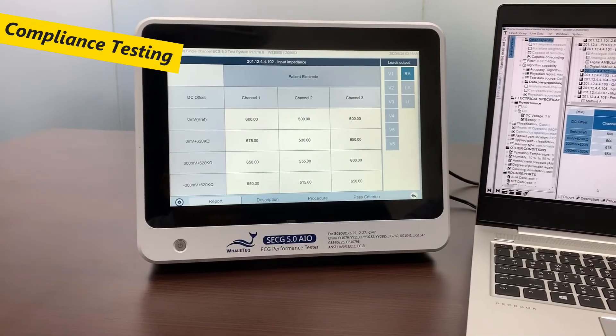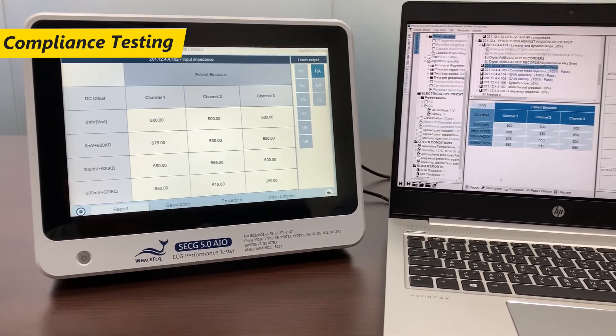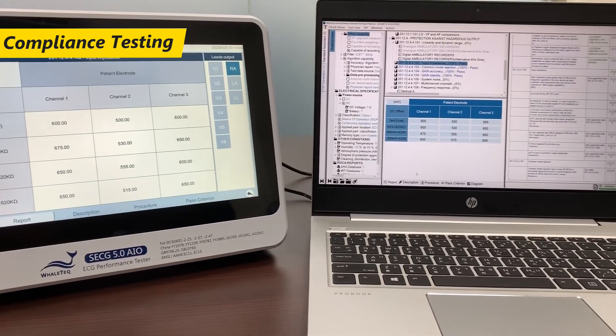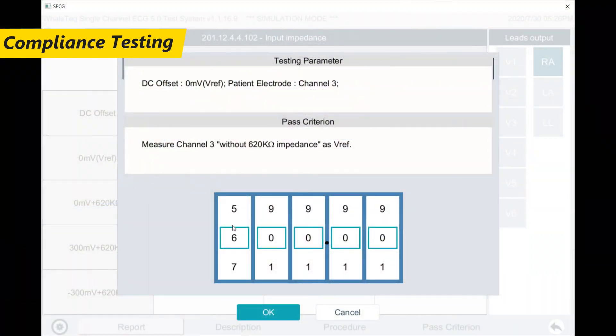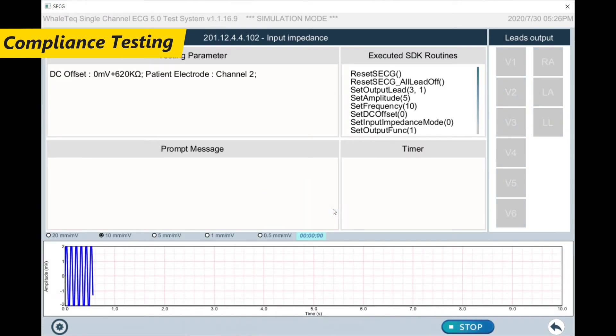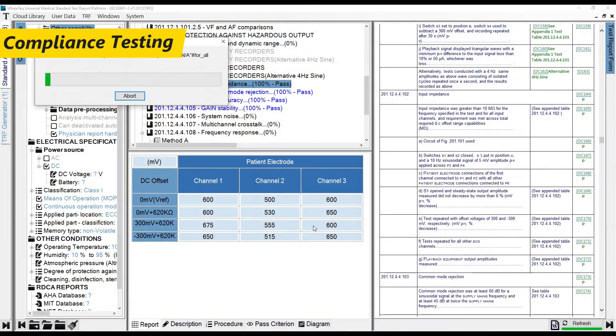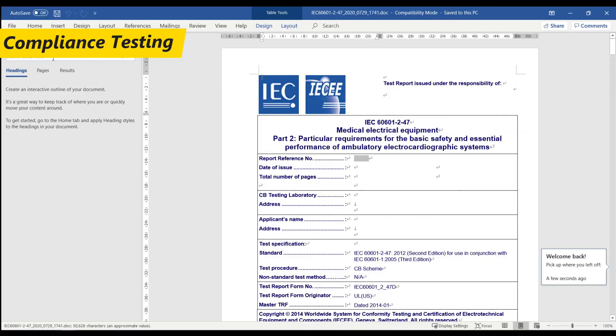As a compliance tool, SECG 5.0's new standard assistant combined with the TRF generator is the most powerful standard testing solution on the market. The redesigned standard assistant can help you with test documentation, progress tracking, and of course, generating standard waveforms. By exporting directly to the WhaleTeq TRF generator, you can create compliance test reports at the click of a button.